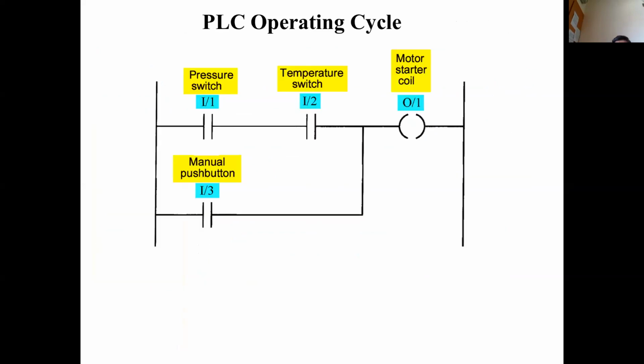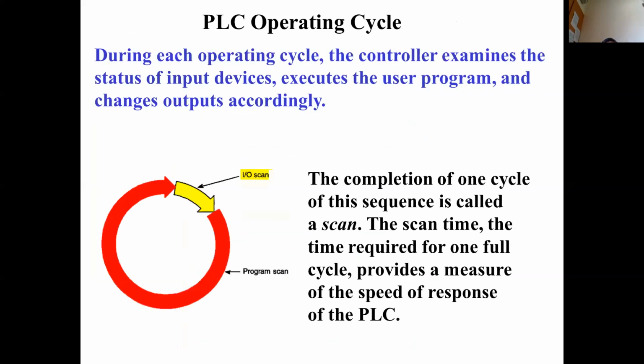Then the PLC scan cycle. So what is the scan cycle of the PLC? First, it will scan the input and output modules: what input and output modules are present, what inputs are present, and what outputs are present. Then it will scan the program. If there are no errors, the program will be executed. Depending upon the status of the inputs, the outputs will be changed according to the program.